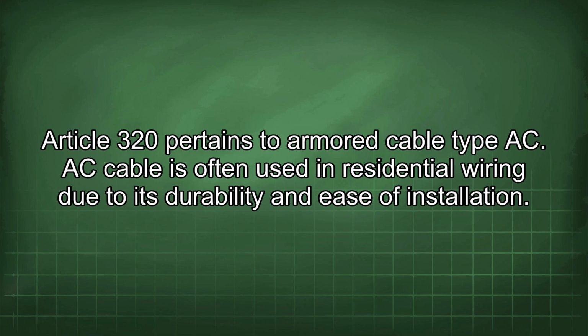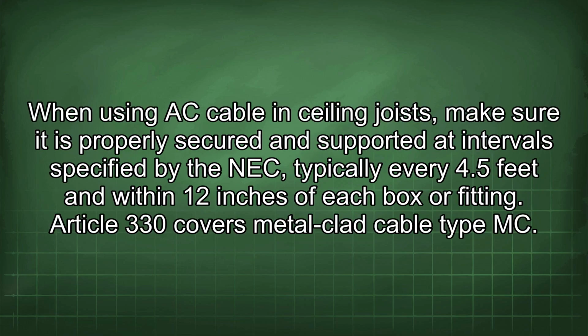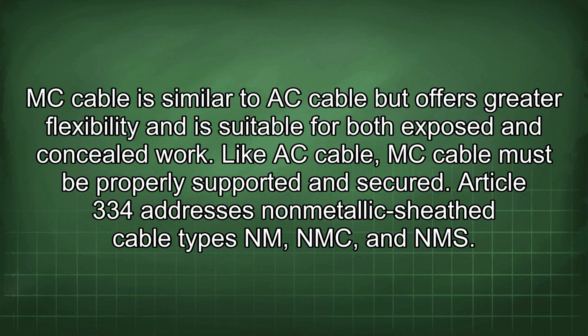Article 320 pertains to armored cable type AC. AC cable is often used in residential wiring due to its durability and ease of installation. When using AC cable in ceiling joists, make sure it is properly secured and supported at intervals specified by the NEC, typically every 4.5 feet and within 12 inches of each box or fitting. Article 330 covers metal-clad cable type MC. MC cable is similar to AC cable but offers greater flexibility and is suitable for both exposed and concealed work. Like AC cable, MC cable must be properly supported and secured.